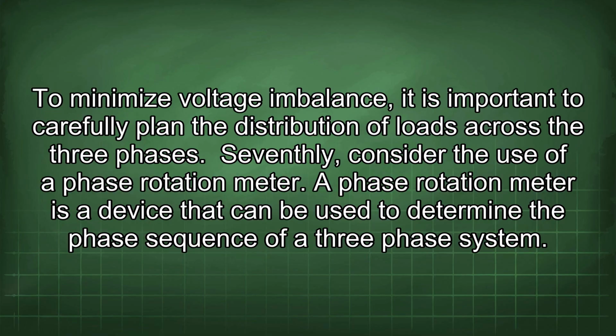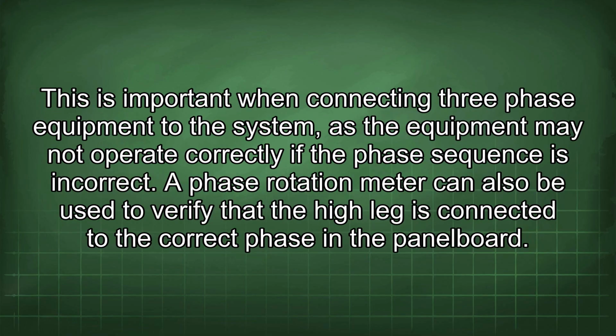Seventhly, consider the use of a phase rotation meter. A phase rotation meter is a device that can be used to determine the phase sequence of a three-phase system. This is important when connecting three-phase equipment to the system, as the equipment may not operate correctly if the phase sequence is incorrect. A phase rotation meter can also be used to verify that the high leg is connected to the correct phase in the panel board.